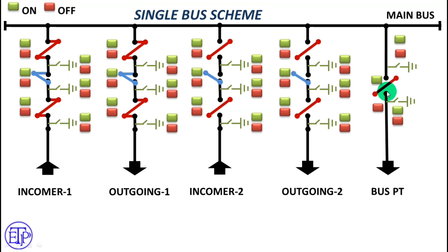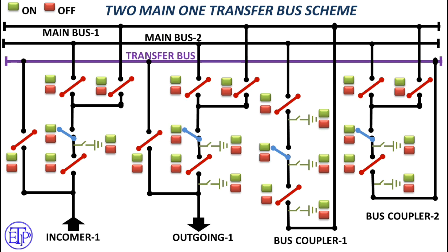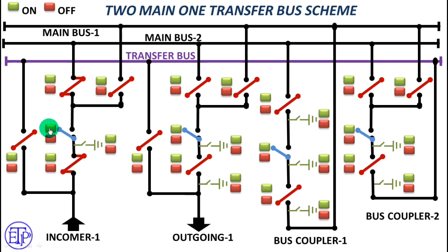Now we will see the most important and interesting busbar scheme — that is the two main and one transfer scheme. Here you will see all the criteria, like there is insignificant change of current. Breaking or making of bus PT implies an insignificant current change. In this section, we will see how the isolator is operated when there is the same voltage at two terminals of the isolator poles. Suppose we have to close incomer 1 to main bus 1 — we will first close this isolator, then this isolator, then close this circuit breaker. This incomer has been connected to main bus 2.